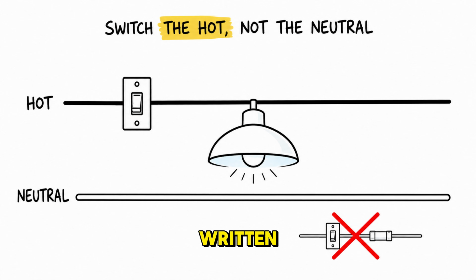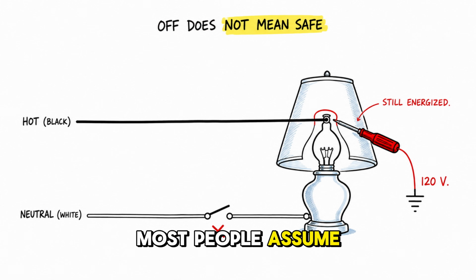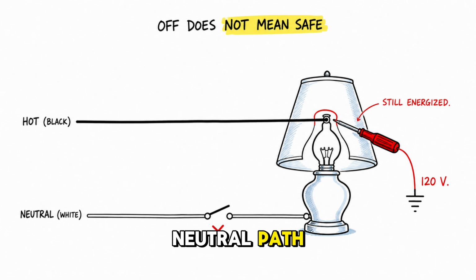Here is a rule that is written into every electrical code across the globe. Never place a switch or a fuse in the neutral wire. Never. Not for any reason. Not even if it seems logical. Most people assume that if you switch off the neutral path, the appliance is turned off and is therefore safe. This assumption is completely wrong, and here is exactly why.